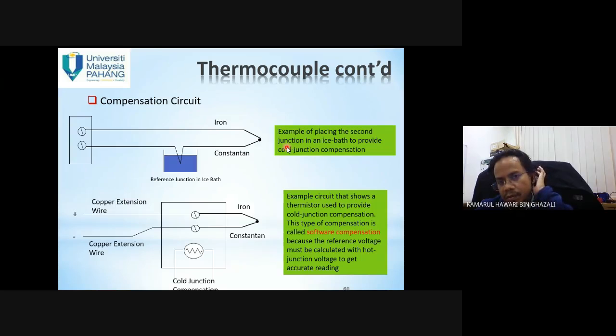Compensation circuit. Okay, example of placing the second junction in an ice bath to provide cold junction compensation. So this is the example circuit that shows a thermistor used to provide cold junction compensation. This type of compensation is called software compensation because the reference voltage must be calculated with the hot junction voltage to get an accurate reading. Okay, compensation circuit.